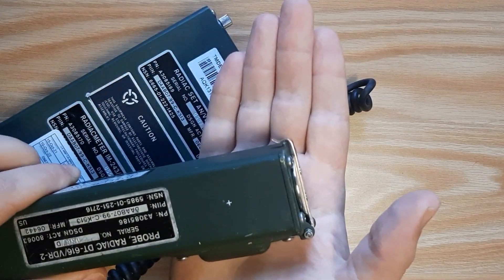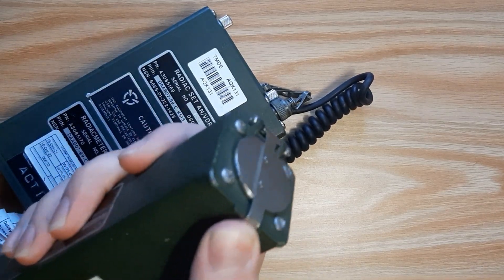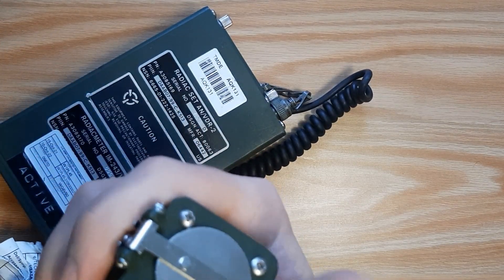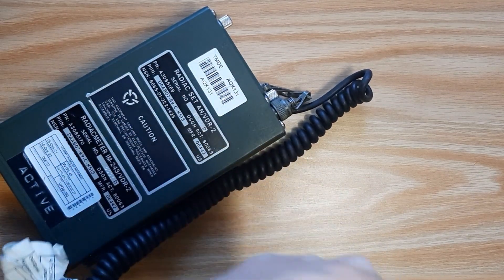Right here we have a beta-gamma probe. It will detect beta and gamma radiation. This is the beta shield — when it is down, it will not detect beta radiation.